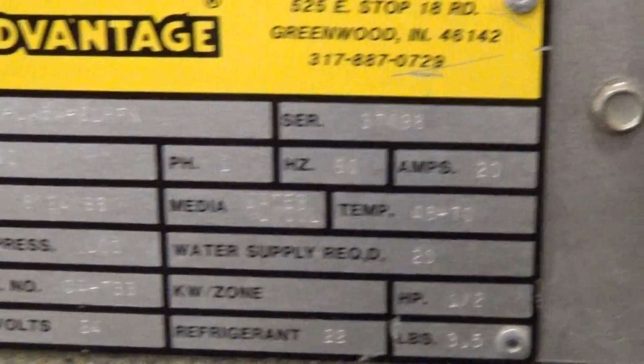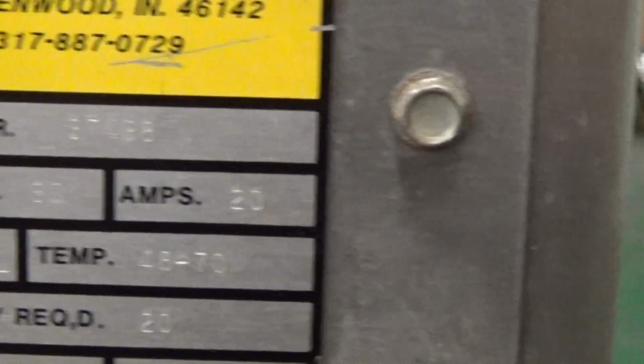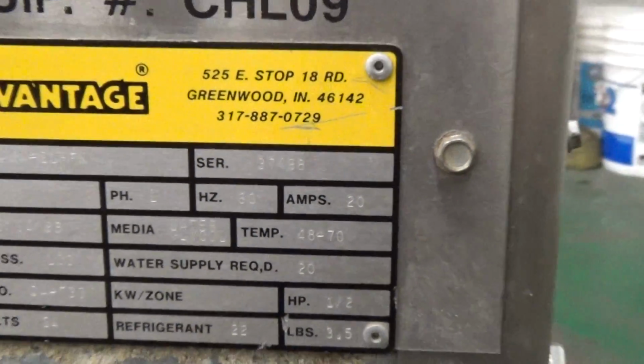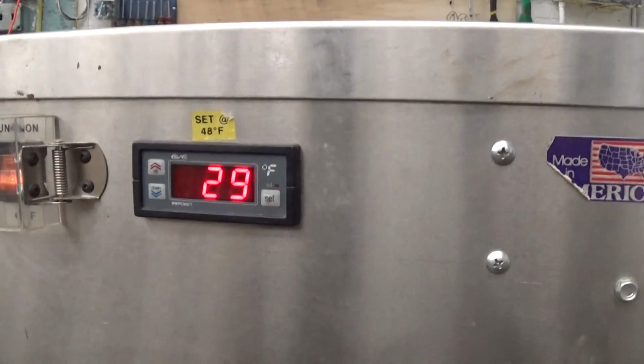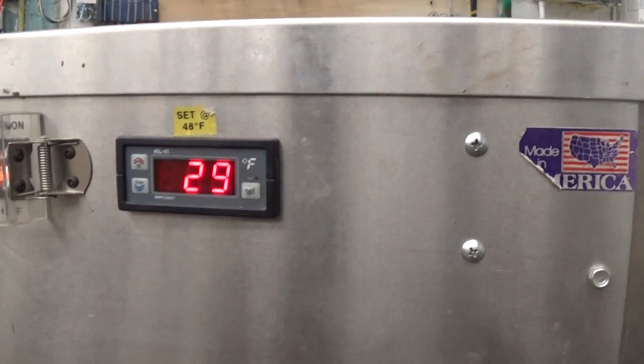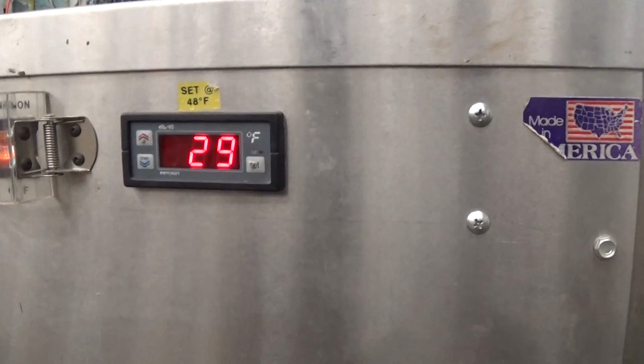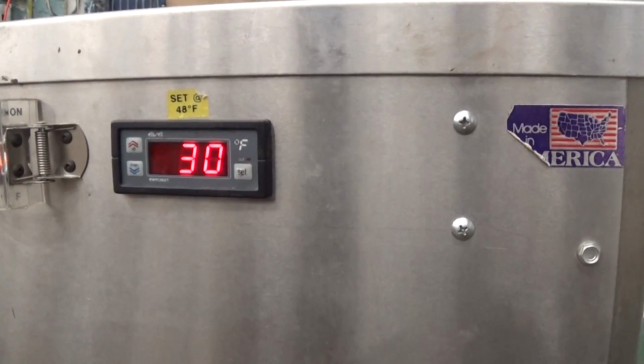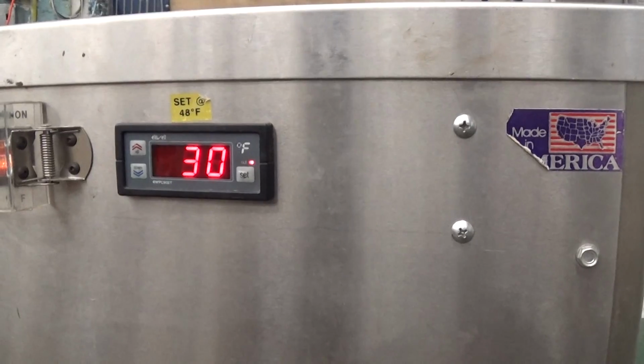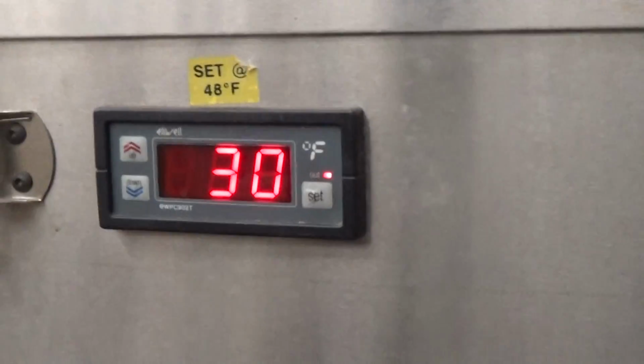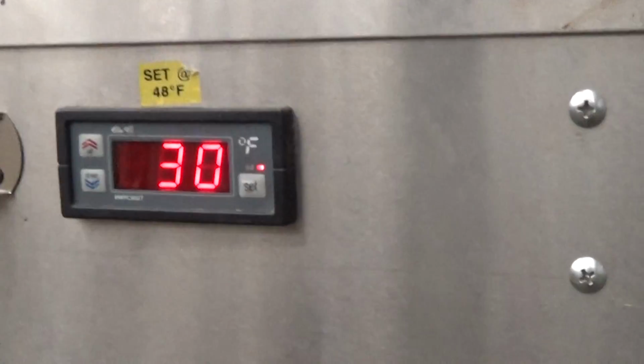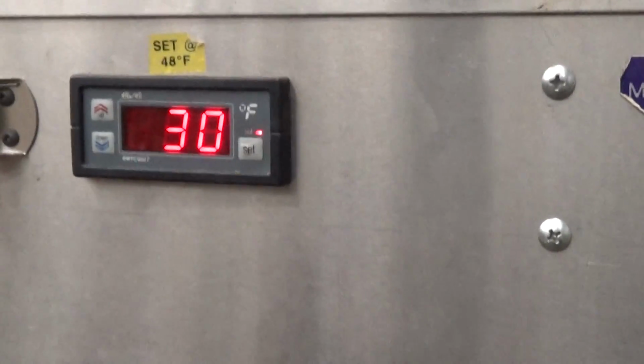The unit is a model IK 1.5A, 230 volt single phase, serial number 37498. We're going to do something a little bit different for our runoff videos. Normally I would let the unit get up to maybe 30 or 40 and show it chill down to the set point. In this case, we've agreed to provide a set point capability of 30 degrees Fahrenheit. So you just heard the unit turn on right now, actually. When it gets to the set point of 30, it's going to chill down to about 2 degrees below set point before it turns off.